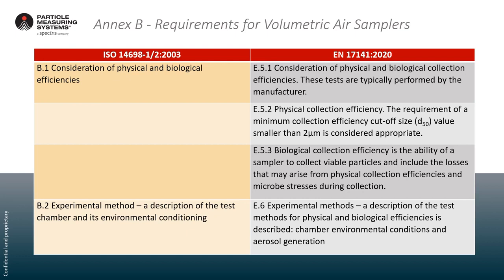One important point is the physical collection efficiency requirement in E5-2: a minimum D50 — that is, 50 percent efficiency at sizes smaller than two microns — is considered appropriate. ISO 14698 used to talk about collection efficiency down to one micron but gave no criteria as to what that value needed to be — it could be 1 percent or 100 percent efficient at one micron. Now with EN 17141, there is a clear criterion: 50 percent efficient at collecting particles smaller than two microns.